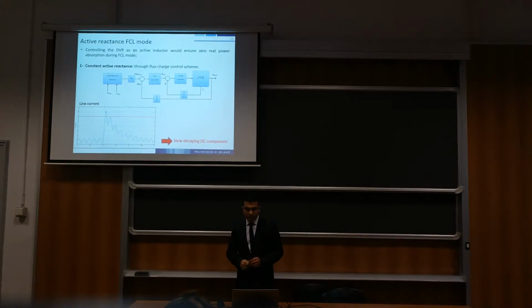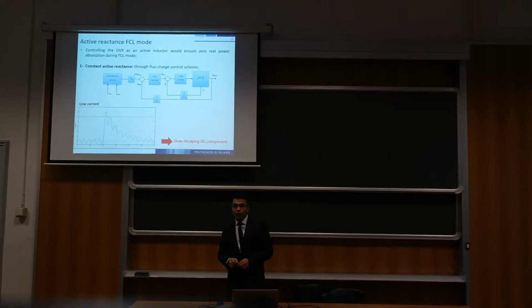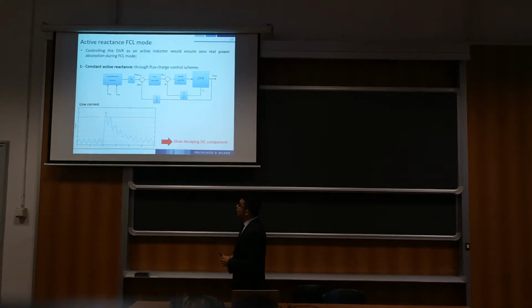For this purpose, the strategy that was proposed in the literature is based on constant active reactance using flux charge control scheme. The problem of this strategy is, again, the high ratio of X over R in the faulted feeder, which results in a slow decaying DC current component. Anyway, the AC component is effectively limited.